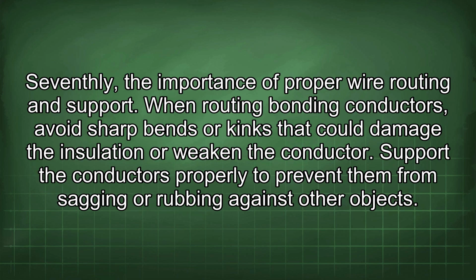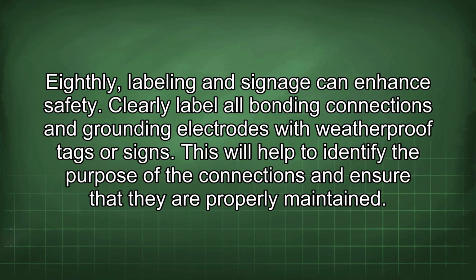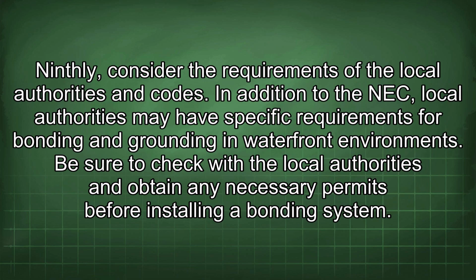rubbing against other objects. Eighthly, labeling and signage can enhance safety. Clearly label all bonding connections and grounding electrodes with weatherproof tags or signs. This will help to identify the purpose of the connections and ensure that they are properly maintained. Ninthly, consider the requirements of the local authorities and codes. In addition to the NEC, local authorities may have specific requirements for bonding and grounding in waterfront environments. Be sure to check with the local authorities and obtain any necessary permits before installing a bonding system.